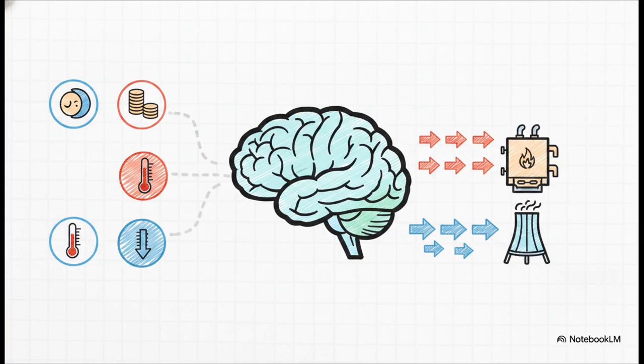Now, the reality is the plant sequence here is far more involved than your standard chiller plant. The controls have to constantly monitor a ton of variables. The time of year, fluctuating utility rates, real-time heating demand, real-time cooling demand. The system is constantly asking itself, are we running because we need chilled water, hot water, both? Are the boilers enabled? Are the cooling towers enabled? It requires incredibly intelligent controls to decide what the entire plant is trying to accomplish at any given millisecond.